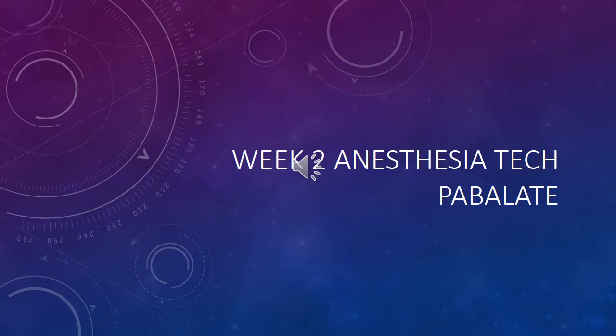The Dräger, you can spin the nitrous all day, nothing will happen. But as soon as you touch the oxygen, then it will rise to meet the 70-30 mixture. And I think that's a key difference between the two main manufacturers. Okay, so you can never give 100% nitrous oxide because it will not work until you open the oxygen flow meter. The moment you touch the oxygen flow meter, it will give as much nitrous as allowable. 70% is the maximum, or 75%.